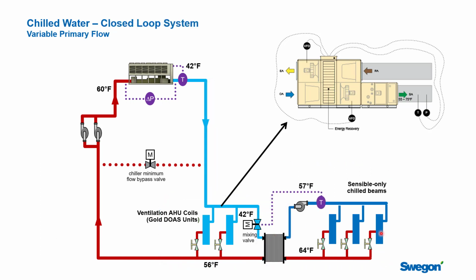Now, in that last slide, we saw that we used a control valve to separate the two water temperature loops, the 42 to 44 degree loop for the air handling units and the 57 degree loop for the chilled beams. You could easily do that with a heat exchanger. We're going to show you this slide once here, but for the rest of them, you'll see us using a mixing valve. Either will work. It really just depends on your preference and your comfort level.